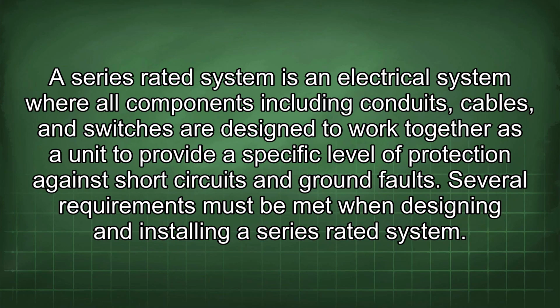A series-rated system is an electrical system where all components, including conduits, cables, and switches, are designed to work together as a unit to provide a specific level of protection against short circuits and ground faults. Several requirements must be met when designing and installing a series-rated system.